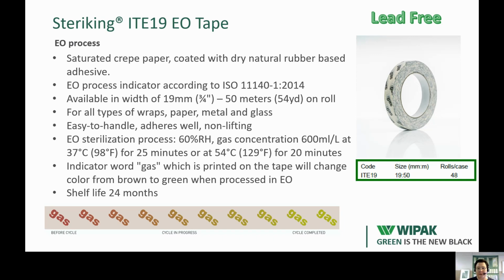And in case it needs to be removed from the metal or glass item sterilized in EO, it also comes off the item after sterilization. It's non-lifting during the sterilization process, but you can take it off if you need to. Then this indicator is supposed to change color in an EO sterilization process that has these parameters: 60% relative humidity and a gas concentration of 600 milligrams per liter, and then either 37 Celsius degrees for 25 minutes or 54 Celsius degrees for 20 minutes. So these are the conditions where this process indicator is supposed to change color.